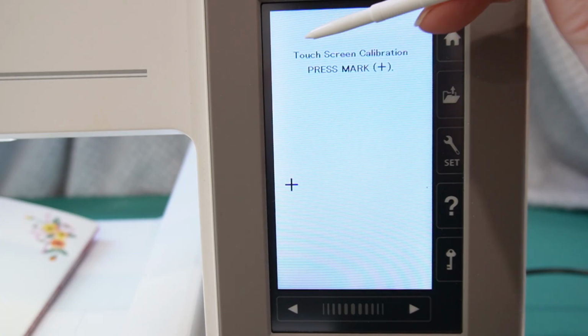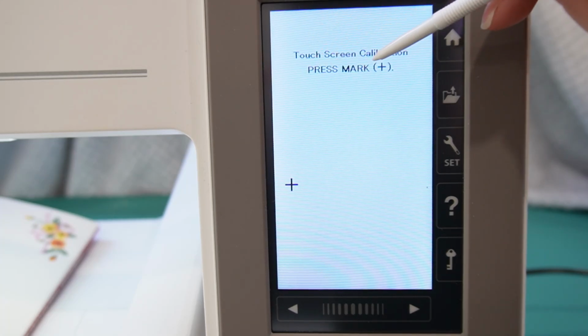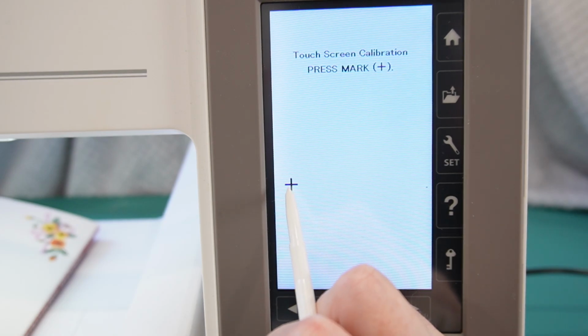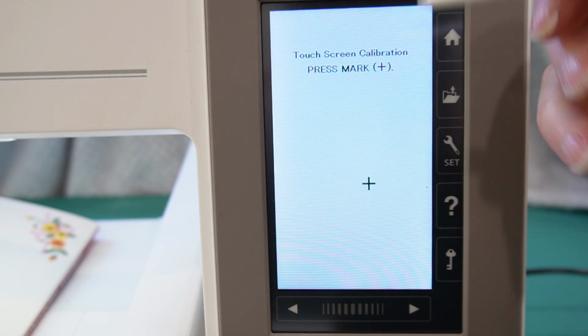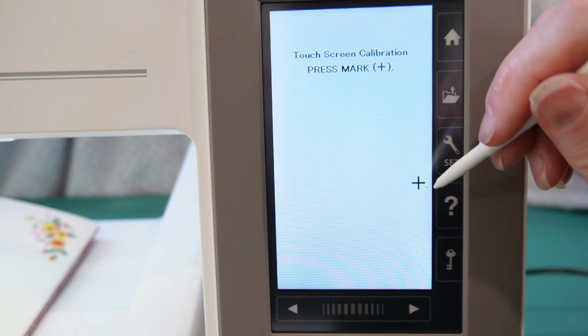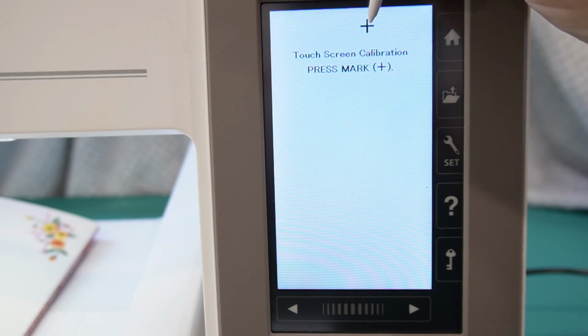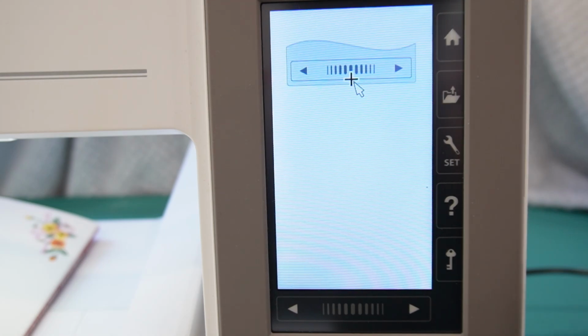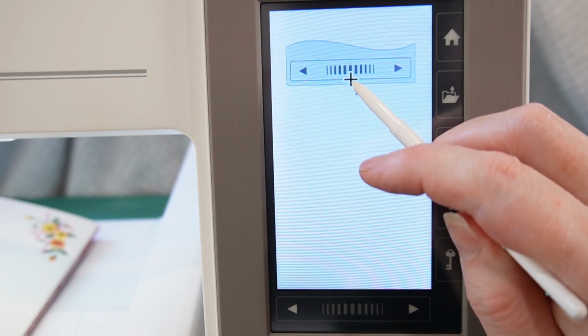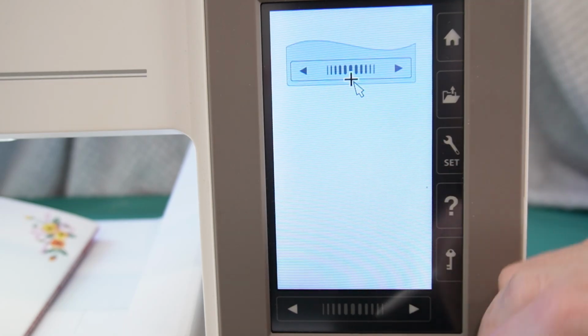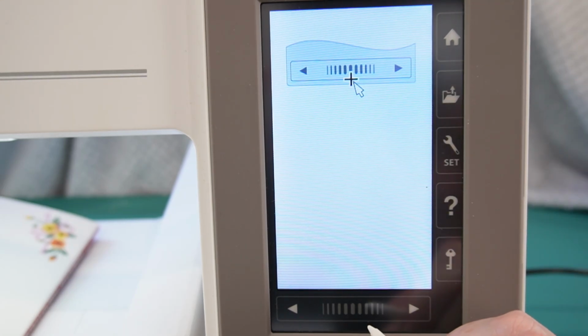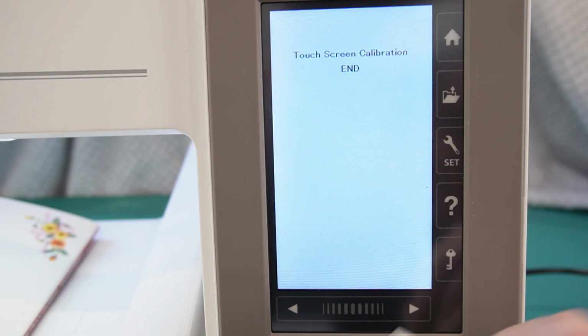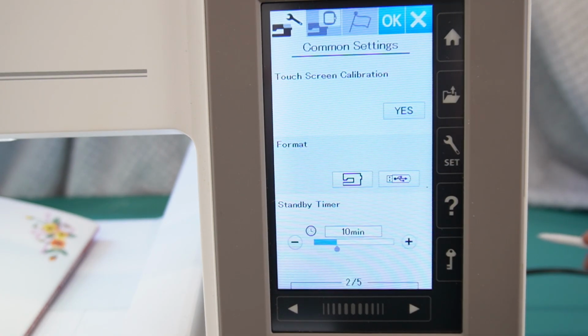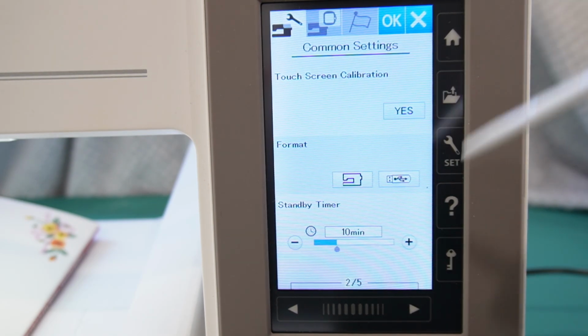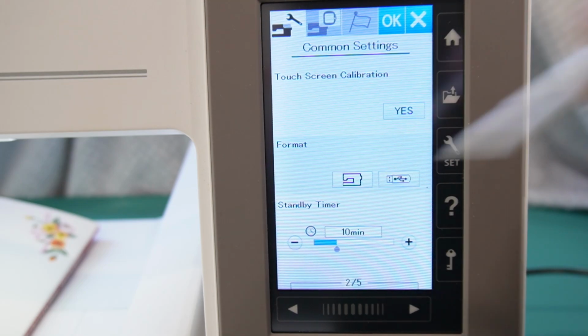Touch screen calibration: press mark plus. So I press with this right in the center of that crosshair, and as I press them all, now it's telling me to press underneath the bar at the bottom here in the middle of it, on the edge there. It has ended now, so now the machine has been calibrated. Everything should work and be perfect when you touch a button. If you get to a point where your buttons are not working, that is what you need to do.